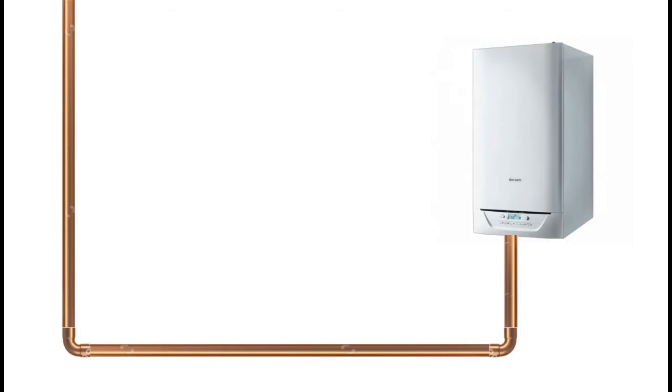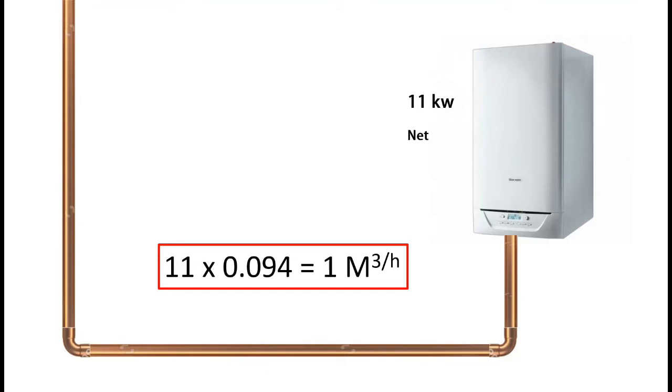This particular boiler is 11 kilowatts net. To work out meters cubed per hour when all you've got is the kilowatt rating, we simply multiply the kilowatts by 0.094. In this case, 11 times 0.094 is one meter cubed per hour.